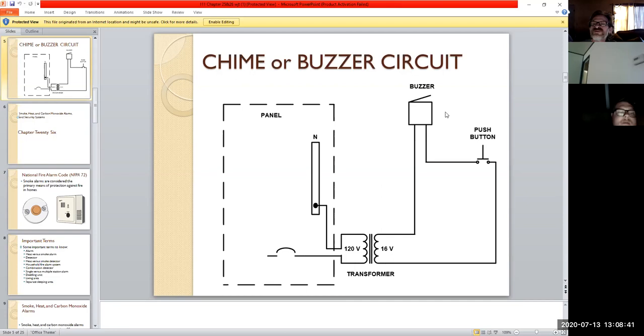Every time you push the button, the buzzer should sound as long as all the circuitry is working correctly. You'll notice it has its own little separate overcurrent protection - there's its own little circuit breaker right here, neutral line, neutral bar.